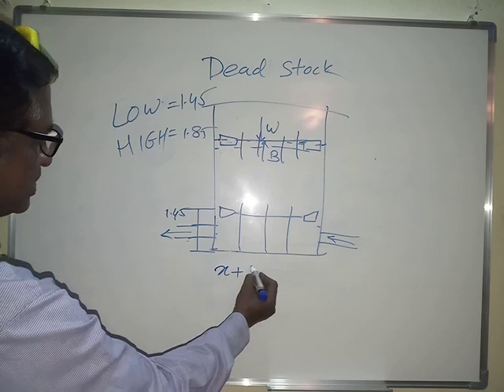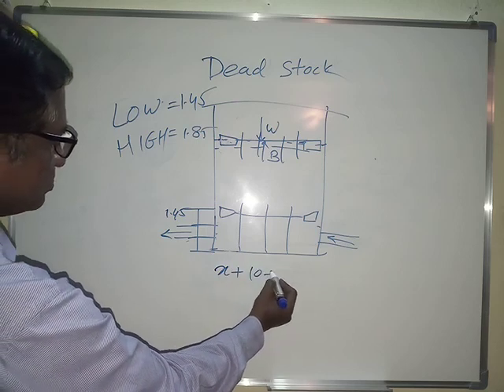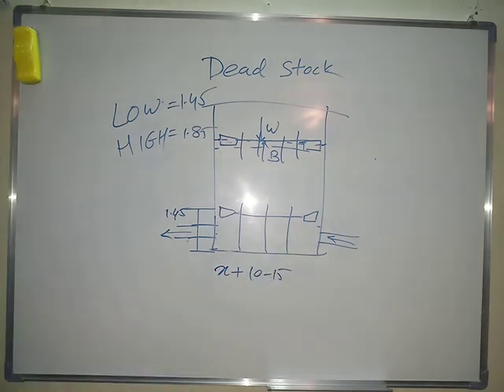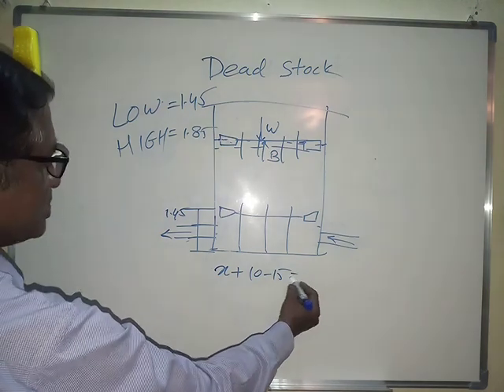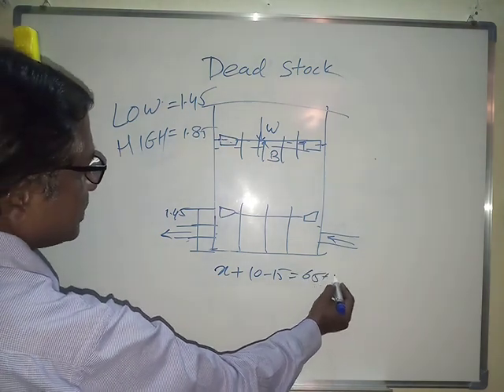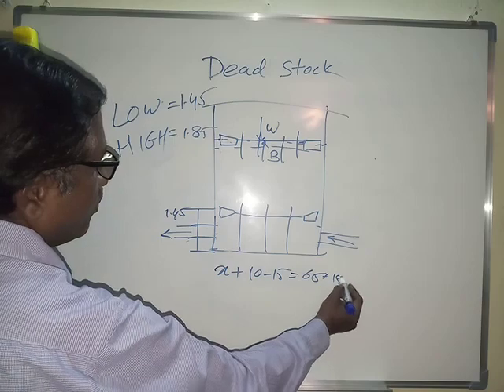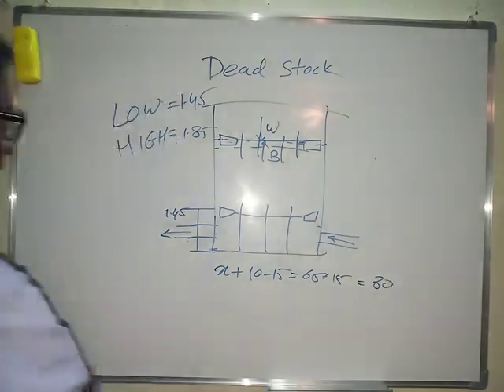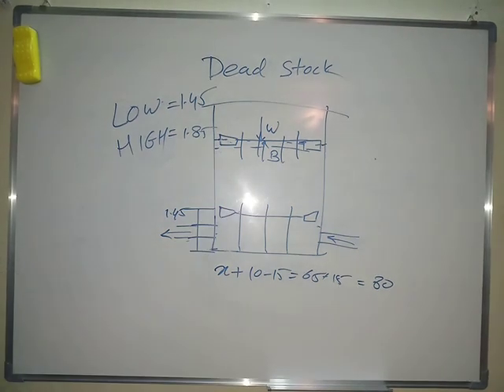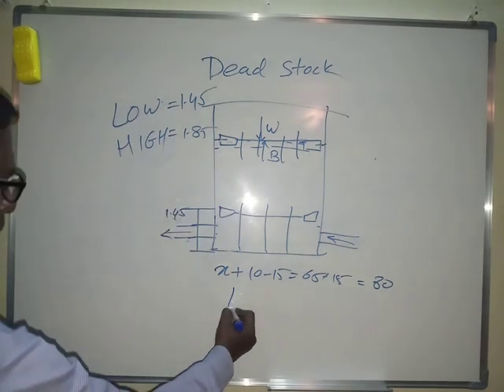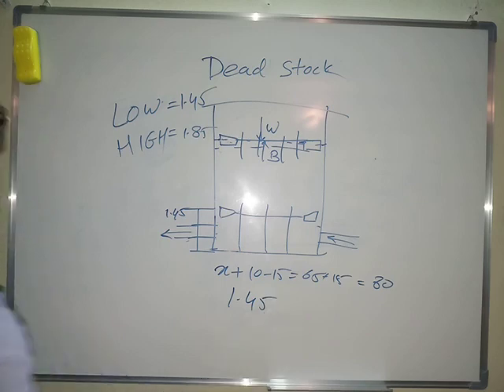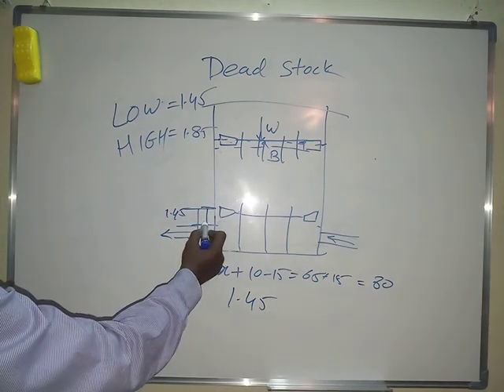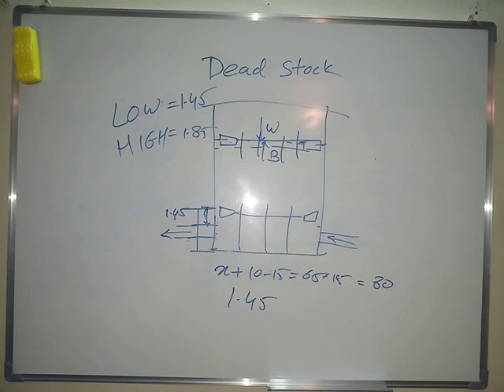In a fixed roof tank we have seen X plus 10 to 15, meaning 65 centimeters plus 15, that is up to 80 centimeters. But in a floating screen or floating roof tank, it is up to 1.45 meters. So there is additional stock blockage in the floating roof or floating screen tank.